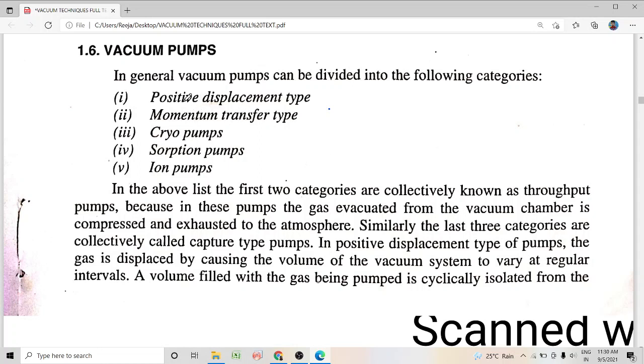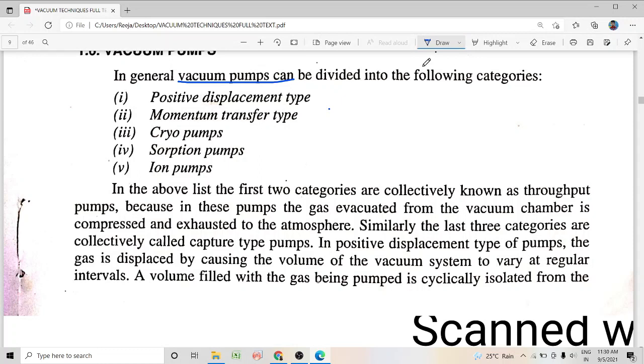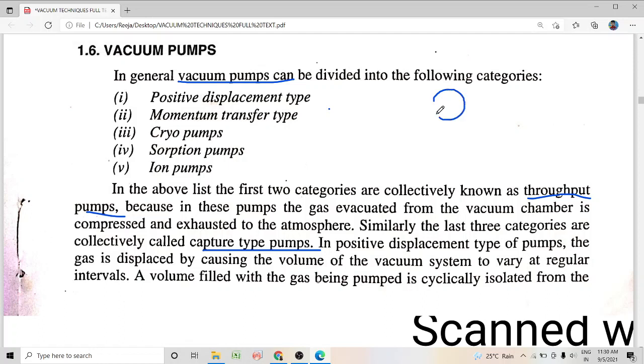Let us first go into the classification of vacuum pumps. Vacuum pumps can be divided into two categories: one is throughput pumps and the other one is capture type pumps. In a throughput pump, the gas taken out from the vacuum chamber — the vessel inside which vacuum is to be created — is compressed and then exhausted to the outside atmosphere by the vacuum pump.